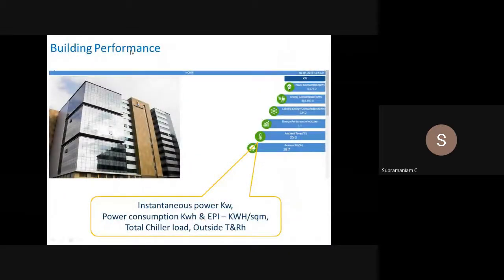From here we can go to this one, which is, for example, what do we get from BMS? These are the values we can get from the BMS screen. At the front screen, it can give you a snapshot of what my power consumption in the building is: 8.8 megawatt, correct? So what was my installed megawatt? Maybe it is 10 or 12. So I know that I am not exceeding, or that I am reaching my threshold value. What is my energy consumption? What is my cooling energy consumption? What is my energy performance indicator? Ambient temperature, ambient humidity. I can get all this, and the owner will be proud. Okay, I know that the equipment is running well. Suppose, imagine the owner has got 10 buildings across Madurai, Trichy, Chennai, so many hospitals at so many places.